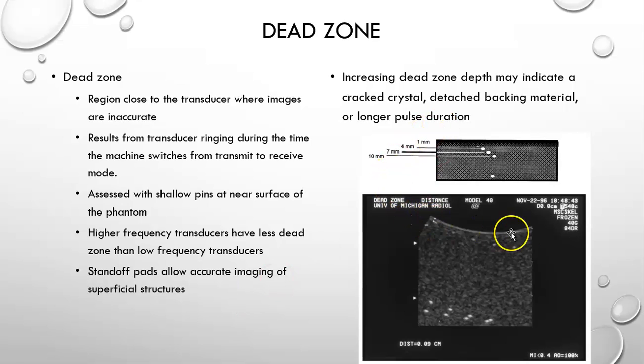If your dead zone suddenly increases in depth, then it may indicate a cracked crystal, detached matching layer or backing layer, or a longer pulse duration. Something has happened to the machine to cause a longer pulse duration.